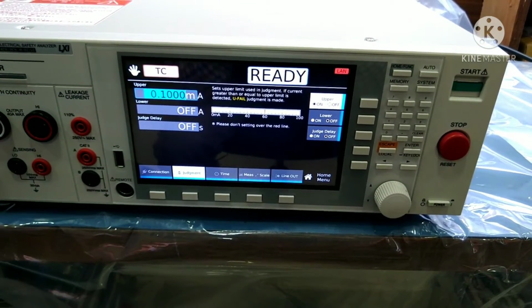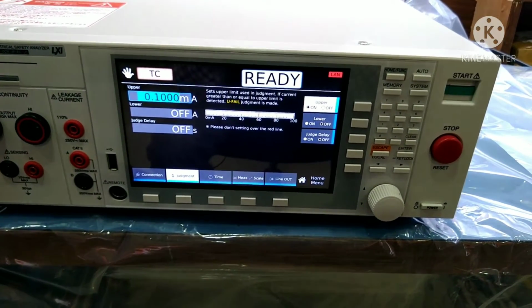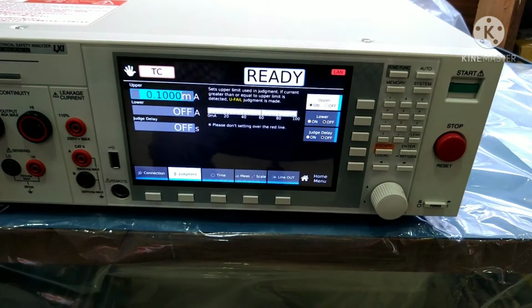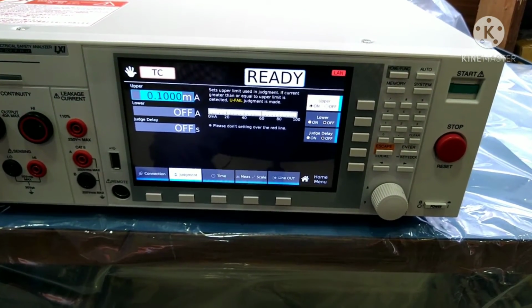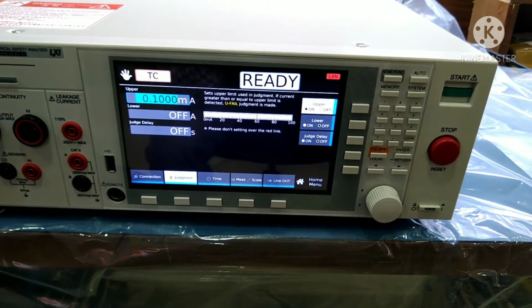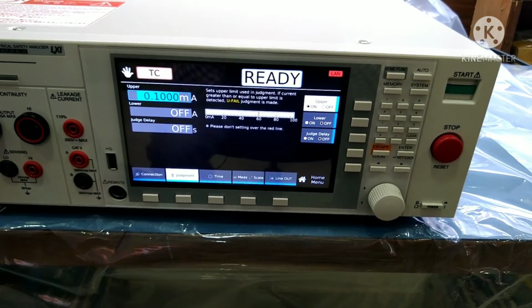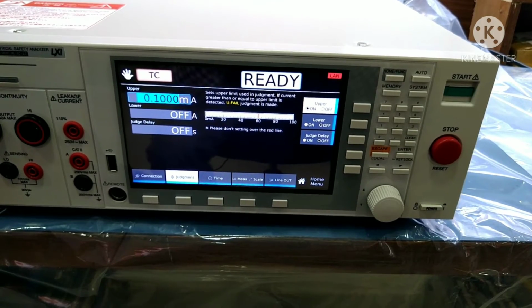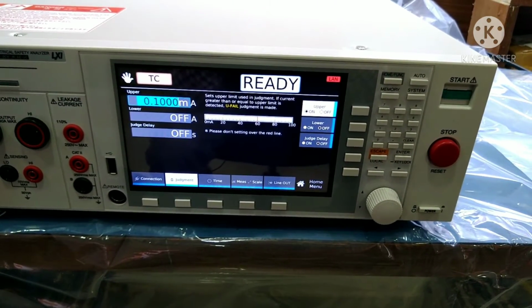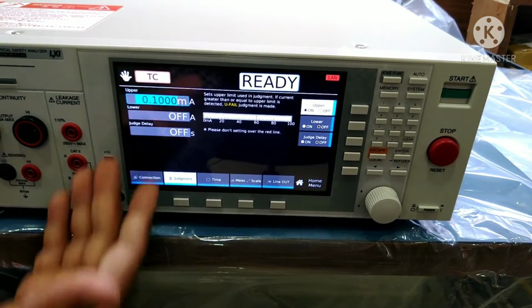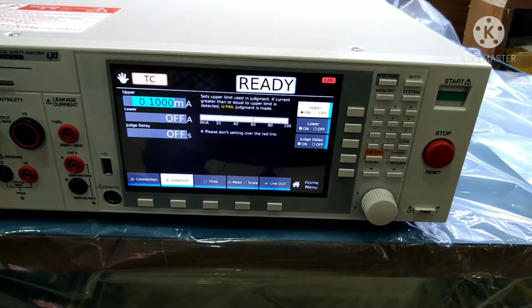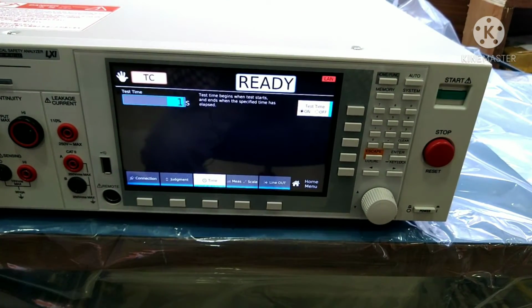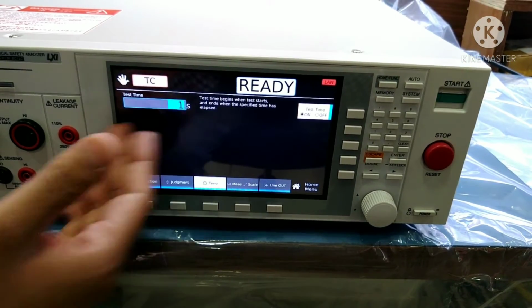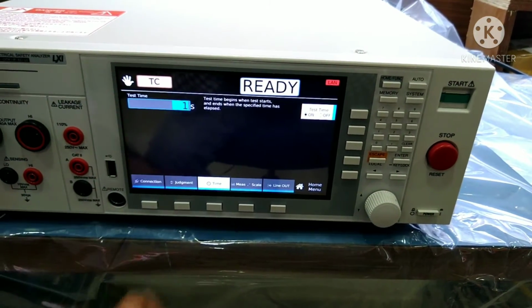Judgment: what the leakage should be within the standards. This is the default, so as per the requirement, you can set the leakage limit here. It should be below this limit, not above the limit. Otherwise it means the device leakage is not as per the standard. So the limit should be within the upper limit. Test time: what time you want to test? By default it is 1 second, so I will keep it 1 second.